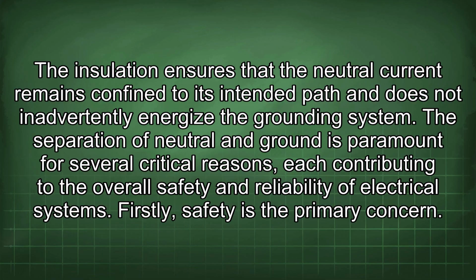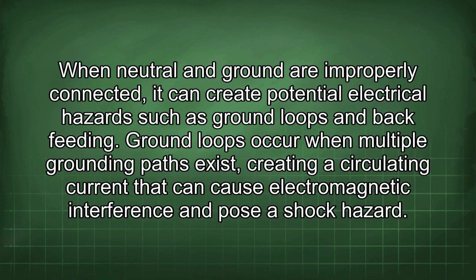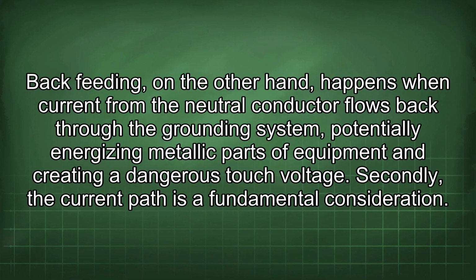This separation of neutral and ground is paramount for several critical reasons, each contributing to the overall safety and reliability of electrical systems. Firstly, safety is the primary concern. When neutral and ground are improperly connected, it can create potential electrical hazards such as ground loops and backfeeding. Ground loops occur when multiple grounding paths exist, creating a circulating current that can cause electromagnetic interference and pose a shock hazard. Backfeeding, on the other hand, happens when current from the neutral conductor flows back through the grounding system, potentially energizing metallic parts of equipment and creating a dangerous touch voltage.